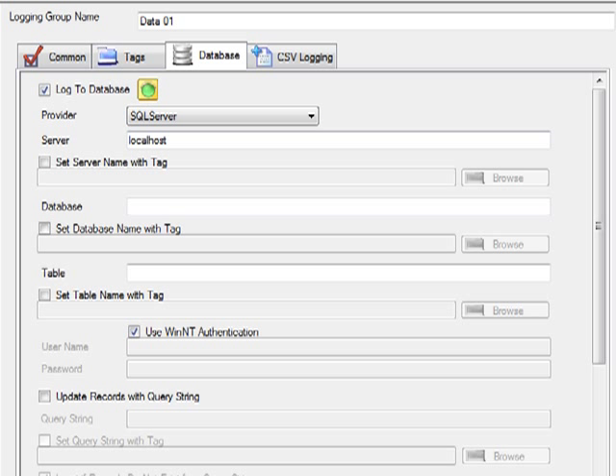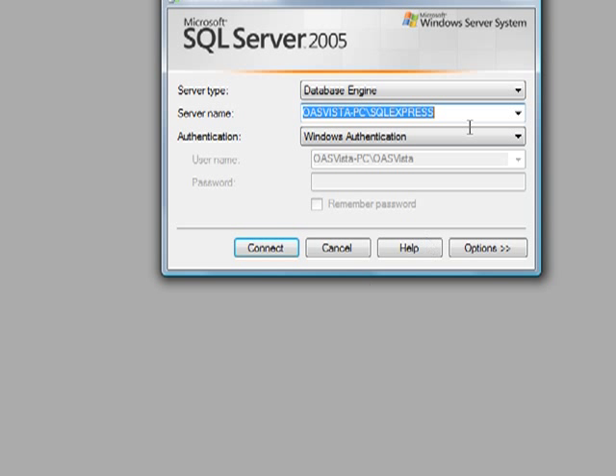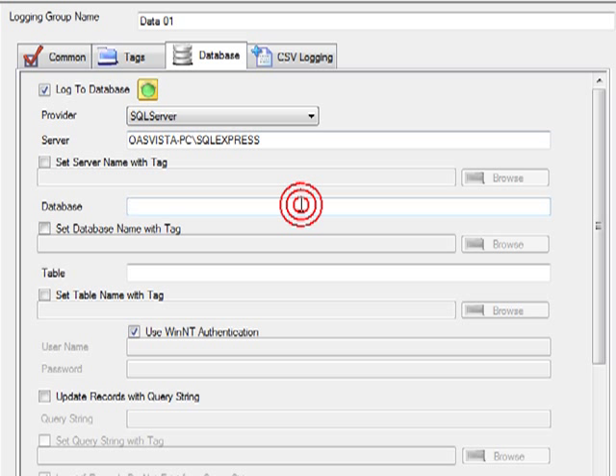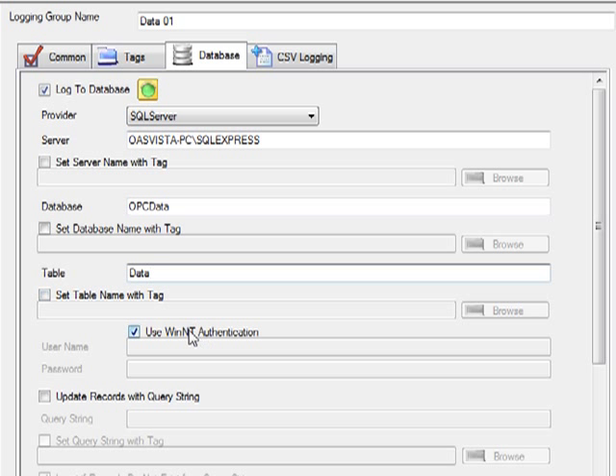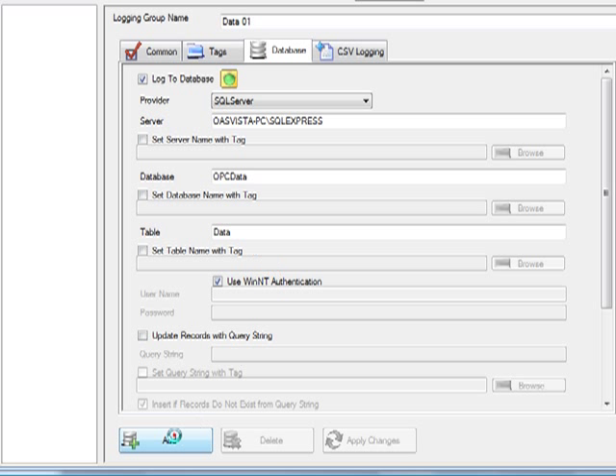It'll create the database, table, and all the field names based upon the tags that you've defined. The first thing we're going to need is the server name that we're going to log to. I'm going to grab that from my SQL Server Management Studio. You can use the free version of Microsoft SQL Server Express if you'd like. We'll enter a database name. I'll use the database name OPCData and a table that doesn't exist as well. Now you can use either Windows Authentication or SQL Server Authentication. We'll add to the configuration. And now we're logging to that database at the one second interval.